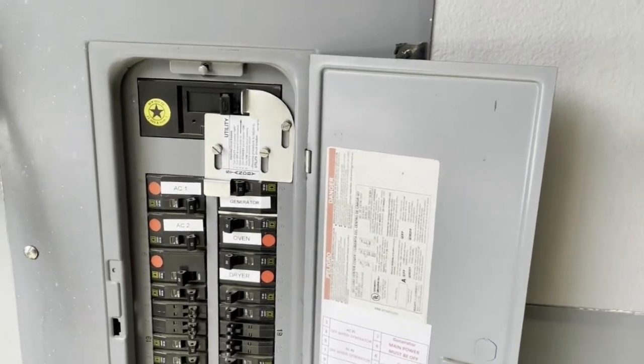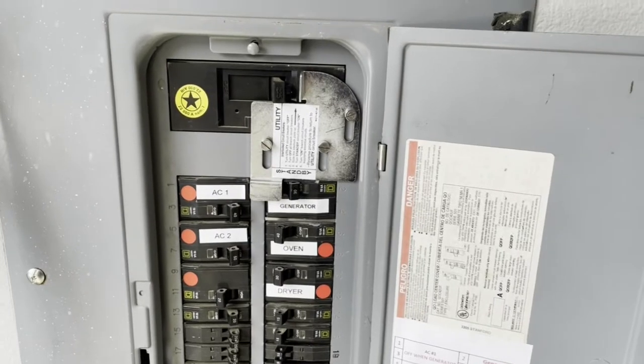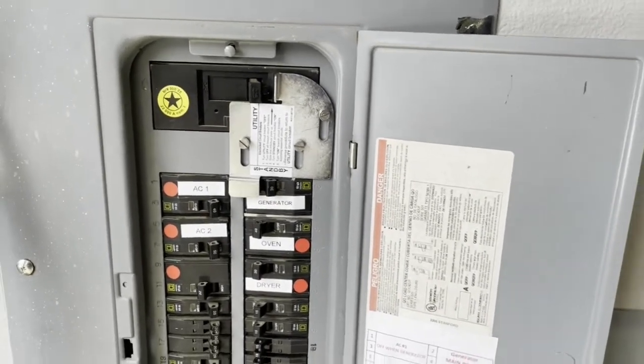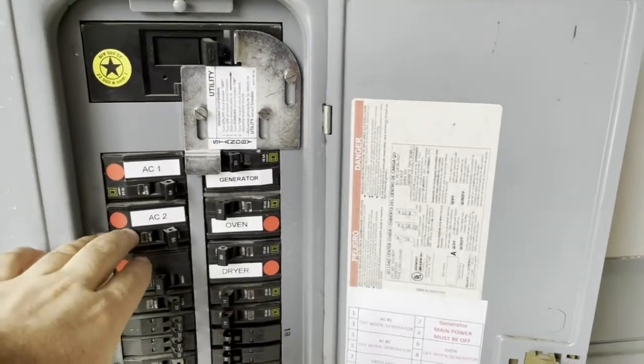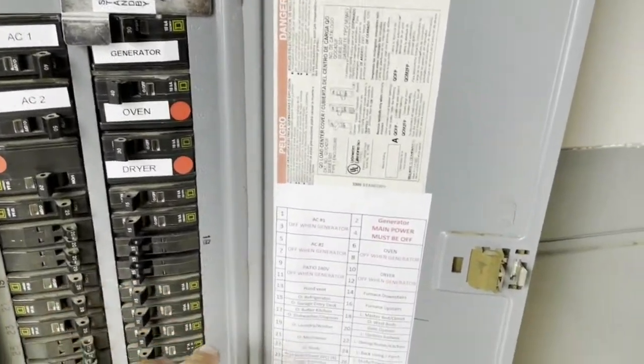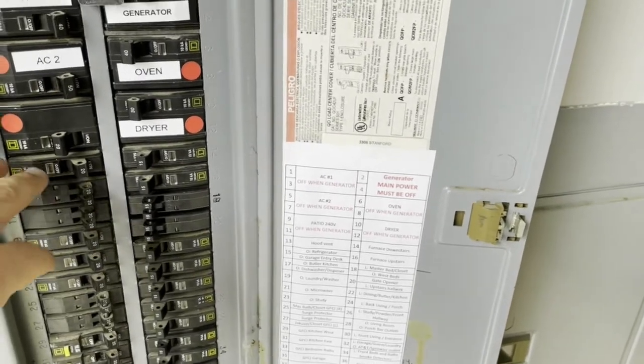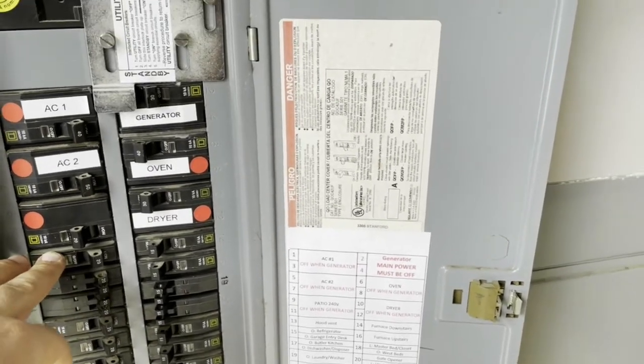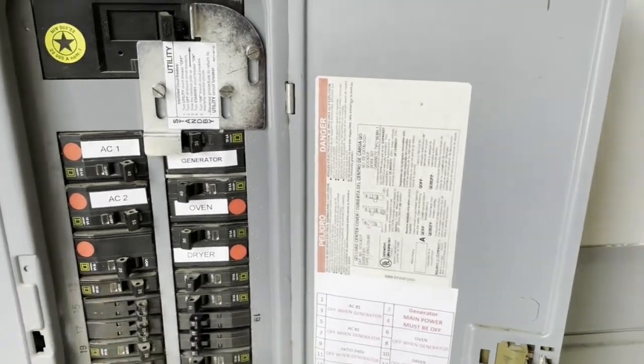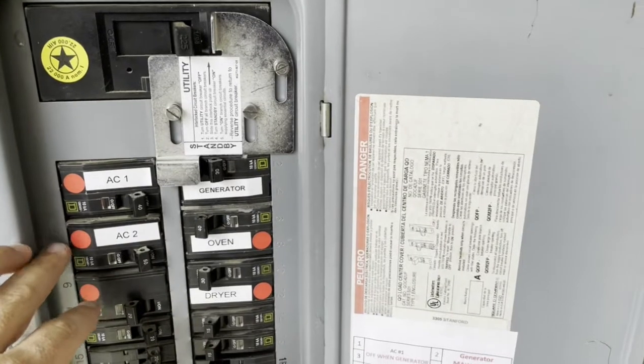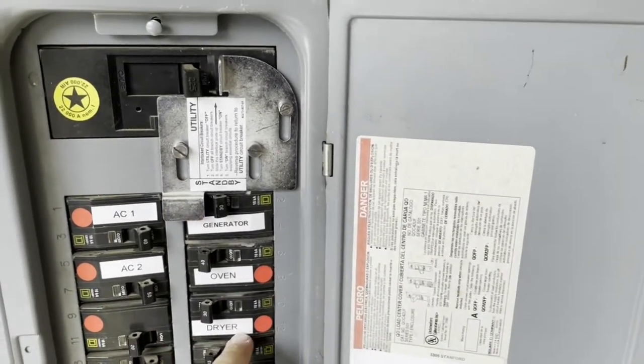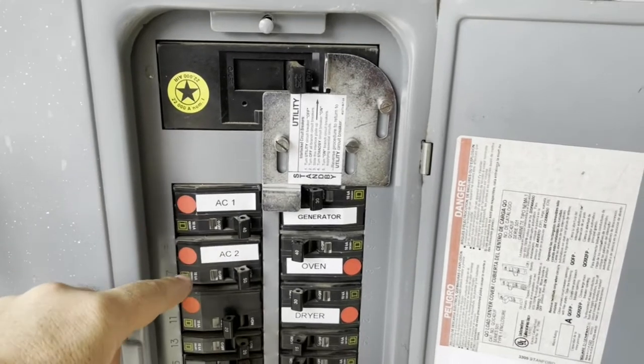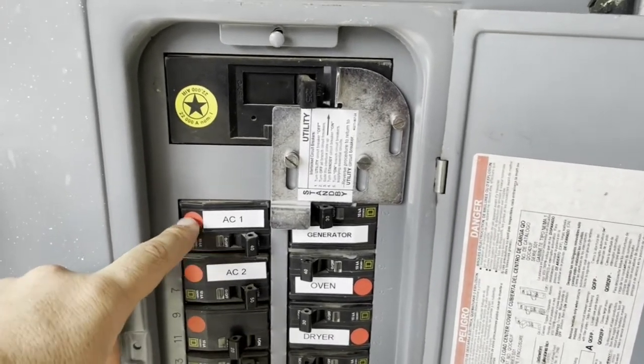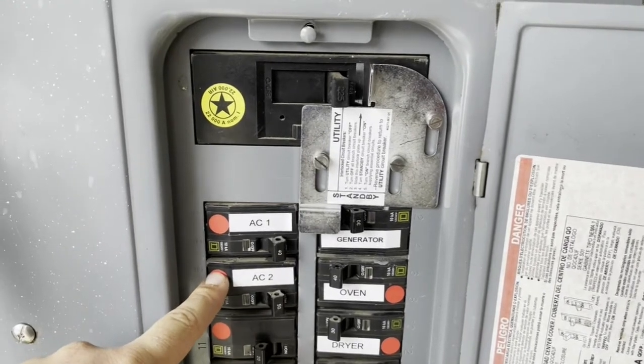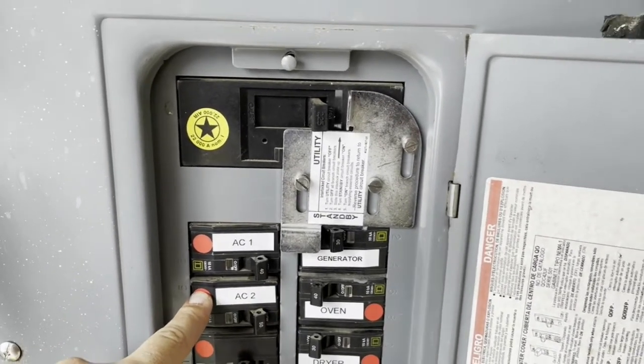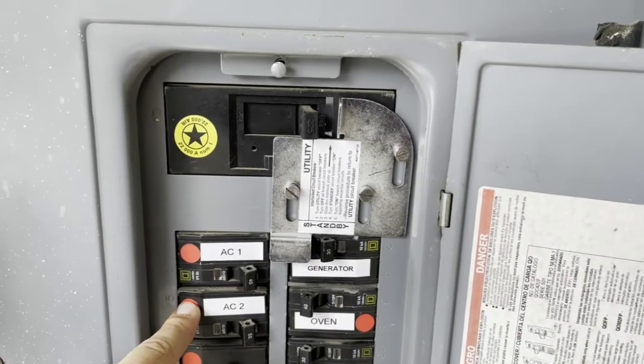They get that power by adding up two different phases of 120 volts, which equals 240. When you open up your panel, which we'll do in a few minutes, you'll see two different lines coming in. It's important to find out which circuit breakers feed which circuits, because when you run your generator, some loads will be extremely high for it and you need to keep them off. A few examples are your electric oven, electric dryer, and air conditioning compressors, because these draw a lot of current during initial startup, so the generator can't feed them unless they're fitted with hard start kits.